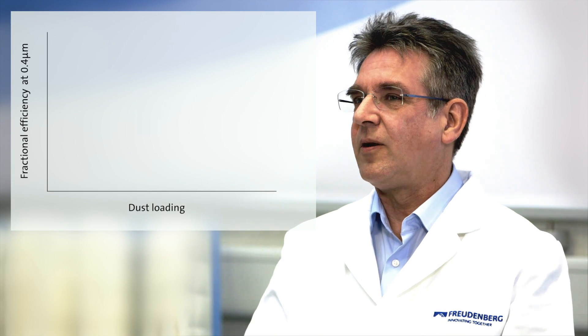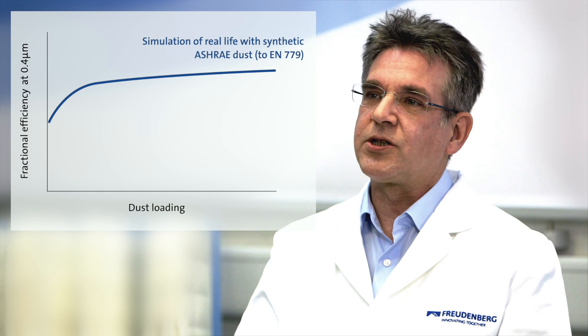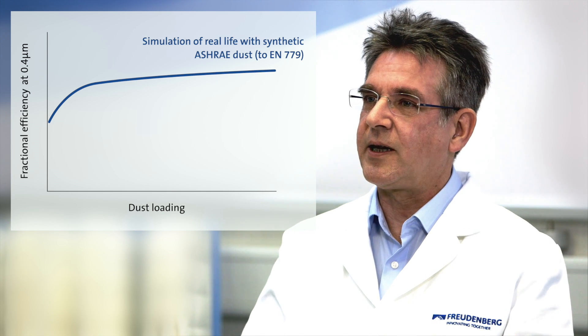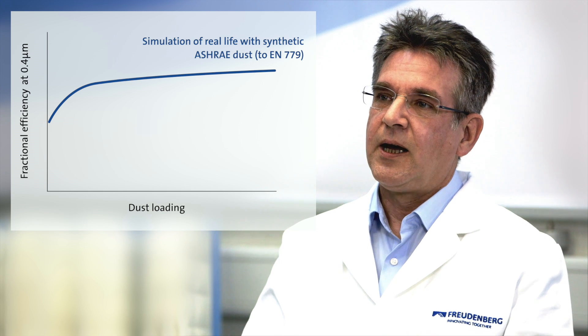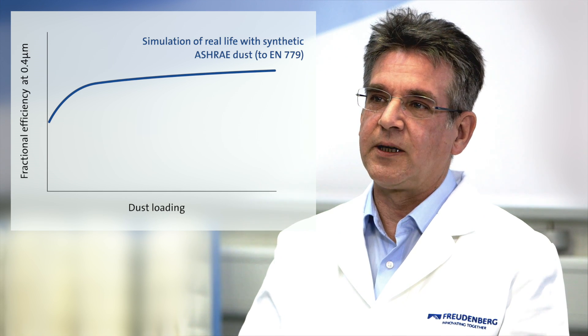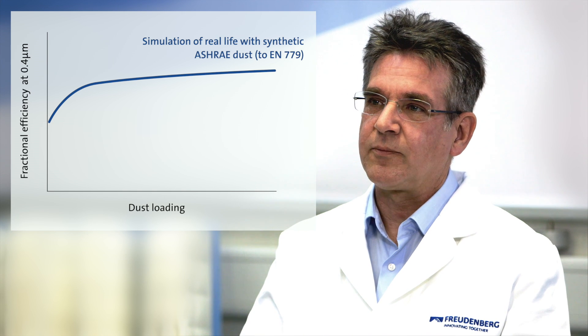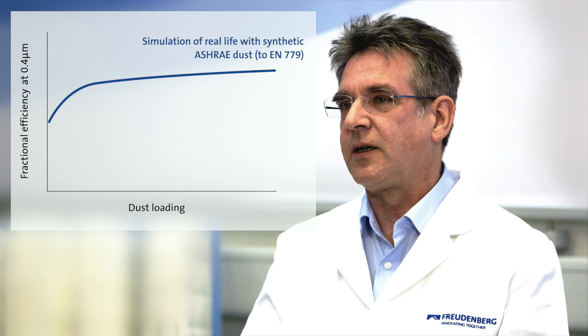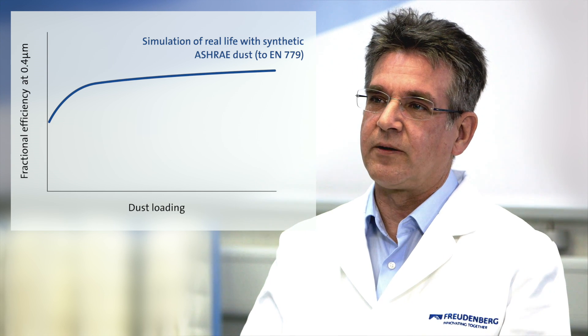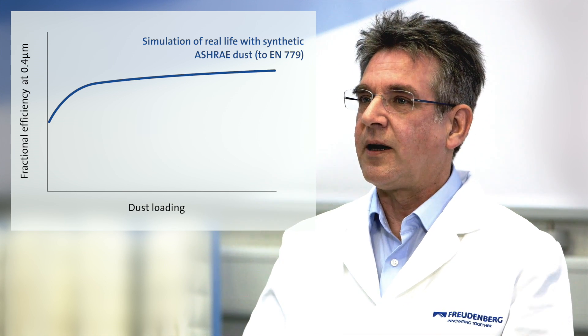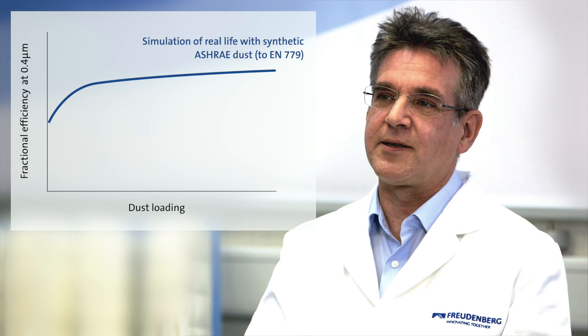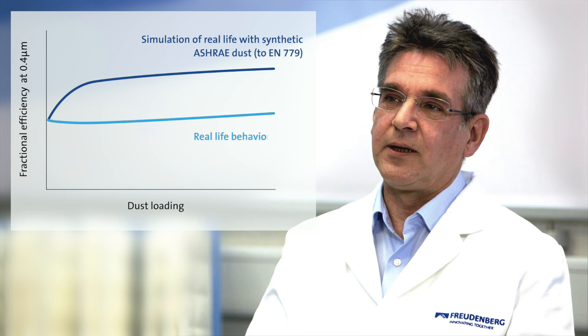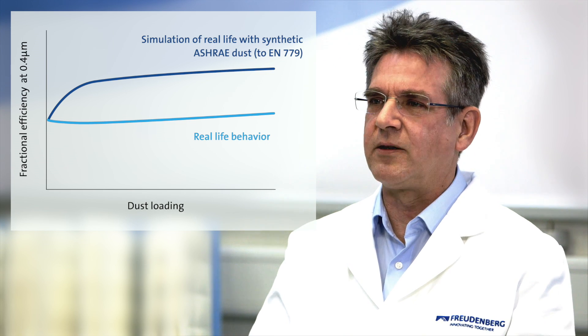The current EN 779 standard evaluates the performance of an air filter as an average over dust loading with a synthetic laboratory dust, so-called ASHRAE dust, and only at a particle size of 0.4 micrometers. The loading with ASHRAE dust doesn't give data which are comparable to real-life performance. Furthermore, the actual ambient aerosol contains a much wider particle size range than only 0.4 micrometers. Therefore, the laboratory data today can be transferred to real-life performance only to a very limited extent.